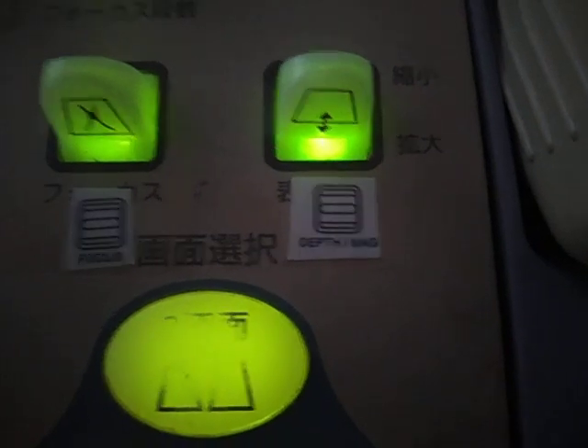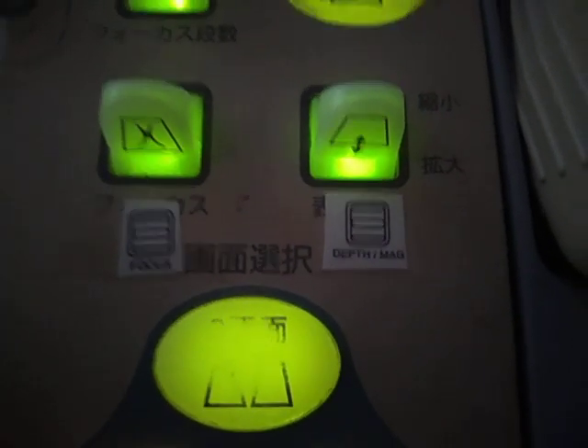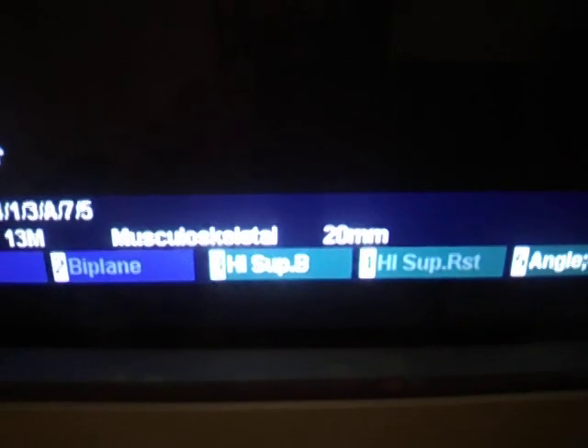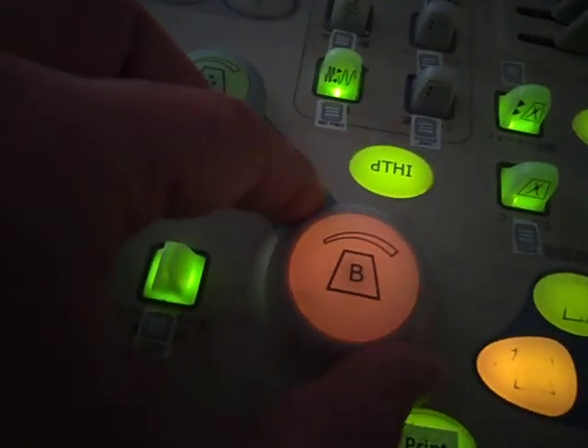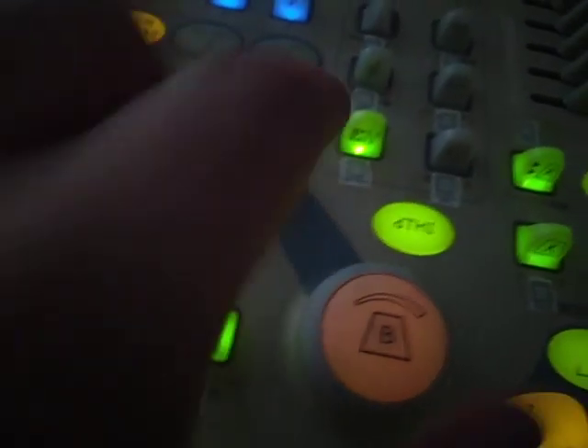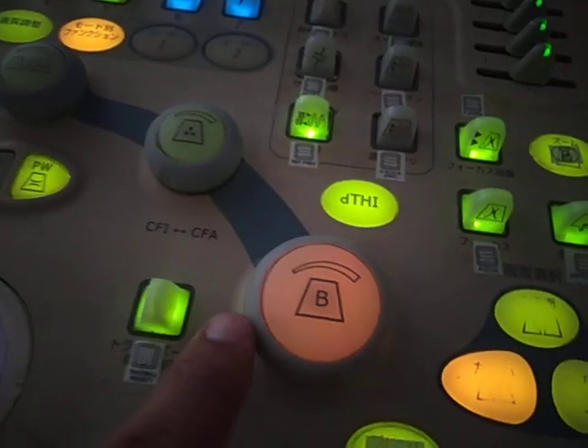So you can see this is the depth, and the other one just next to it is the focus. Depth is, for example, if you're moving from superficial to deeper structure, you can increase or decrease the depth. Right now our depth is set at 20 millimeter. I'm sorry, but my mobile's camera is not really very good. So the depth, focus, the mode, and around this mode, turning the knob clockwise is increasing the gain, and counterclockwise, it's decreasing the gain. So let me recall again: the mode, the gain, the focus, and the depth. These three are really very important.